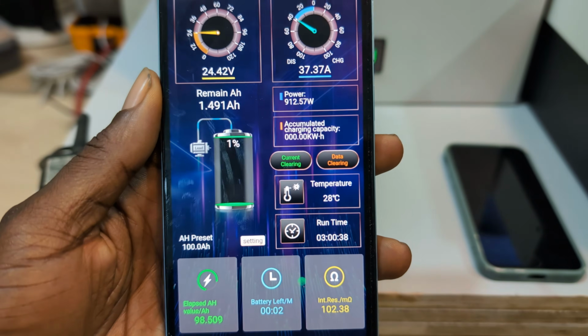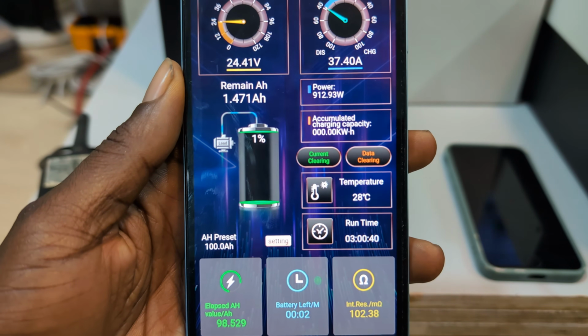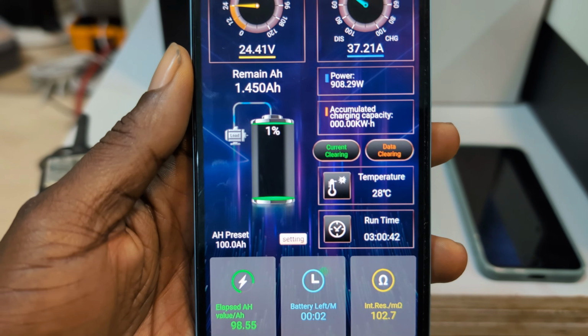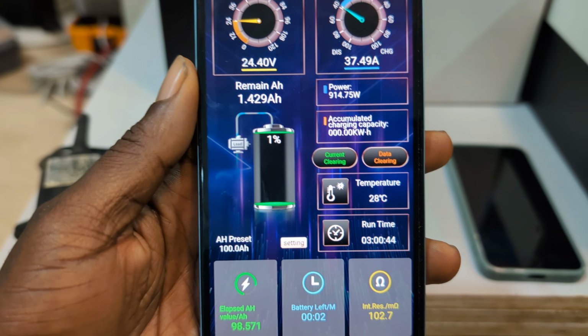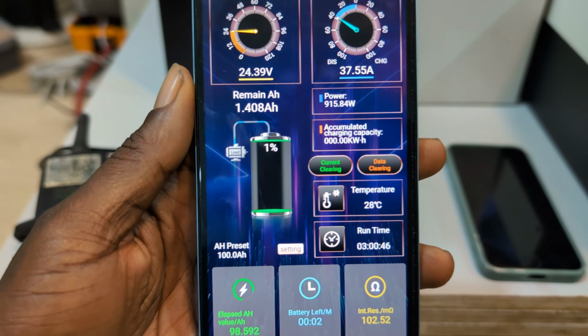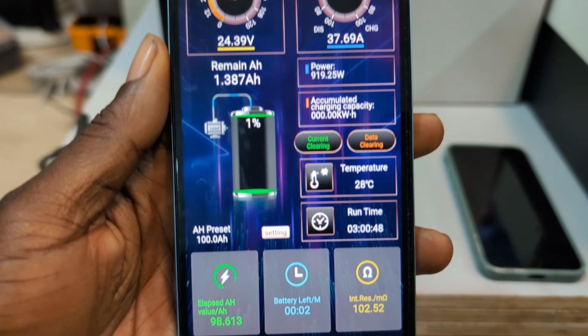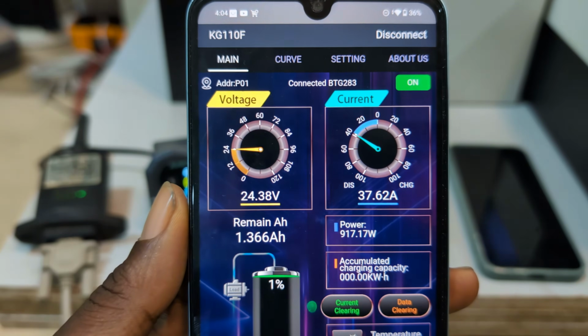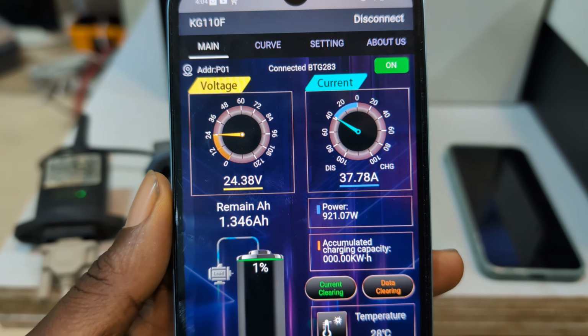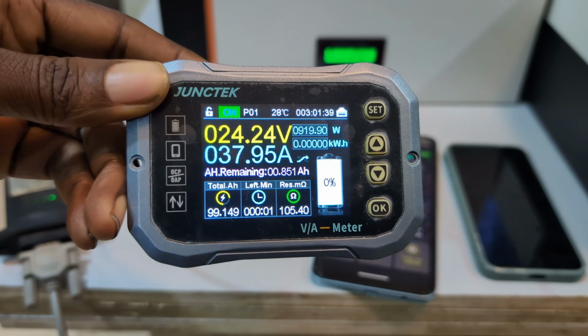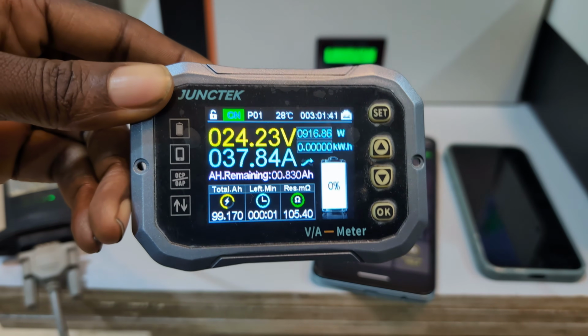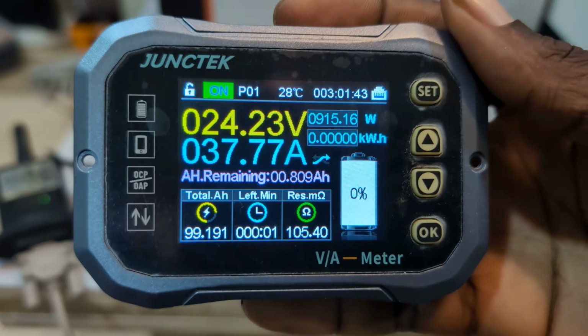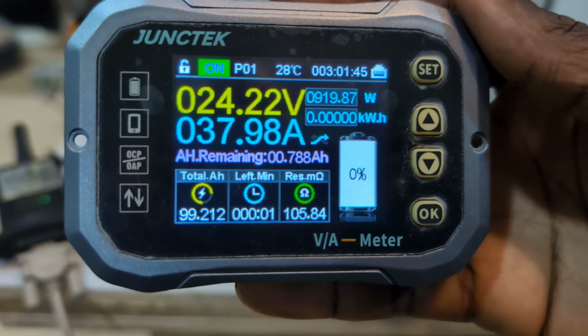When cutting off at 24 volts, you already use all the capacity in the battery. So there's no point saying you are doing 80% DOD or 100% DOD. If you set cutoff voltage to be 24 volts, automatically you are using all the capacity you have in the battery. 99 amp hours now, and our voltage is still way above 24. This is a great battery in my opinion.